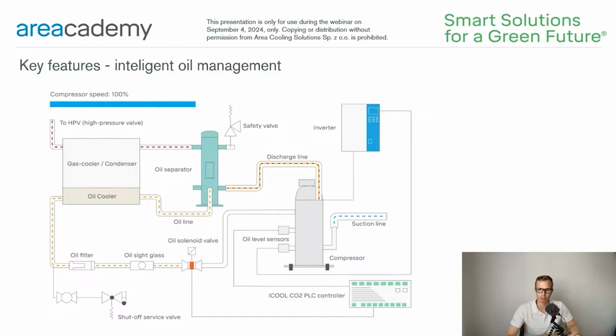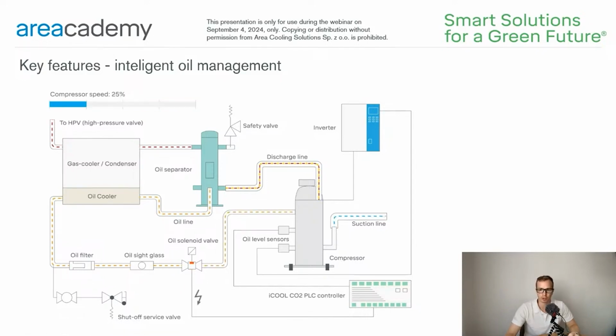The visualization presents the fully equipped oil line in iCool 15 CO2. The oil line includes an oil separator, oil cooler, oil mechanical filter, the sight glass, solenoid valve, elastic injection hose, and the minimum and maximum oil level sensors on the compressors. There is also a dedicated shut-off oil service valve on the service panel. The solenoid valve controls the proper amount of oil inside the compressor.